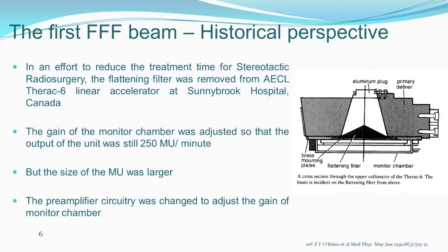Let me go a little bit into the genesis of the FFF beam and where it started. I think it was early in the 90s, 1991, there was a publication by O'Brien from the Sunnybrook Hospital in Canada, where they wanted to do stereotactic radiosurgery and finish the treatment faster, so they wanted to increase the dose rate and thus removed the flattening filter. After removing it, the monitor chamber was adjusted to keep the same output of 250 MU per minute, but the size of the MU was made larger.